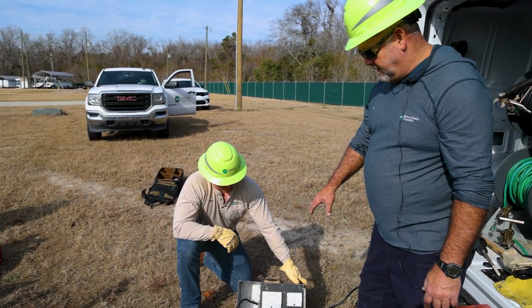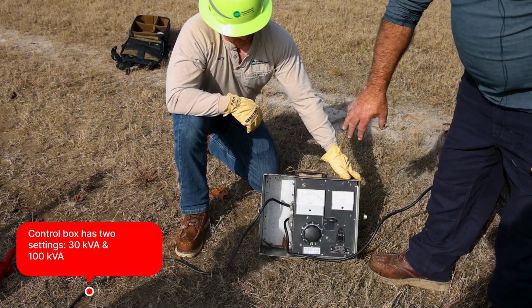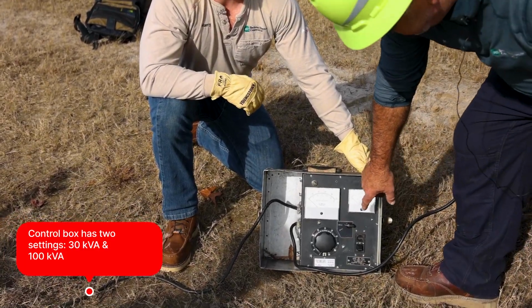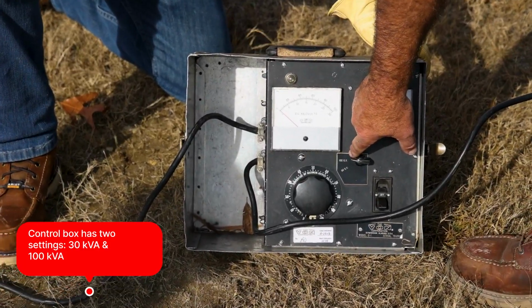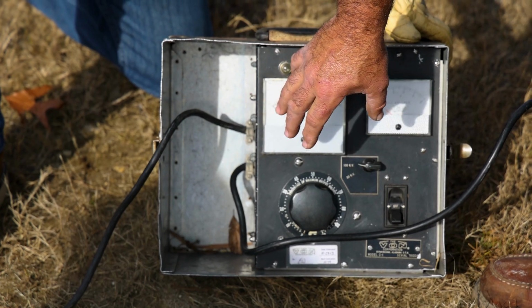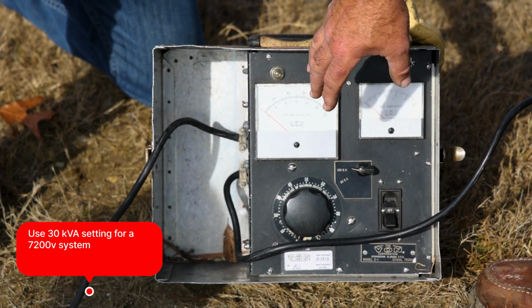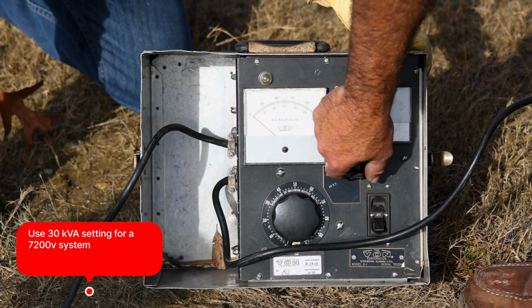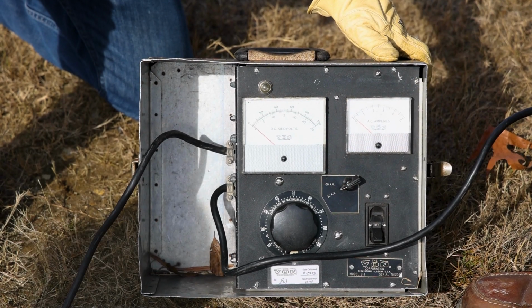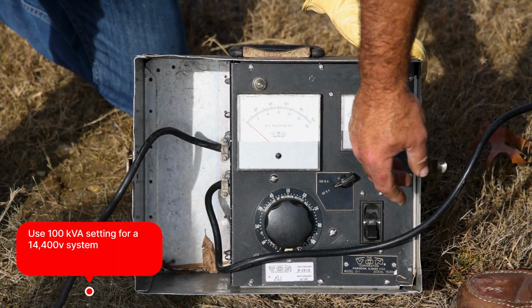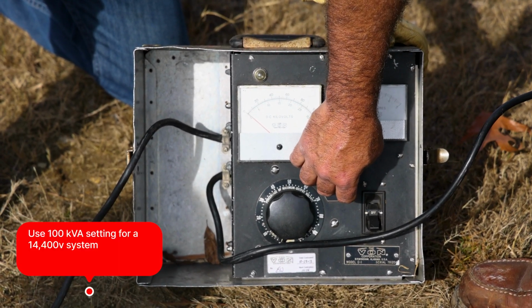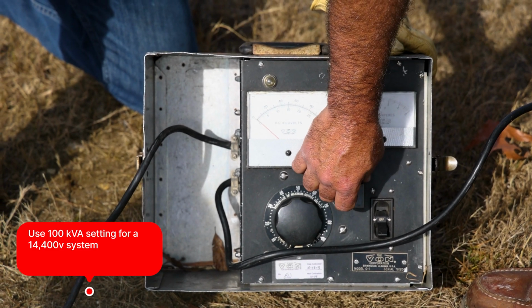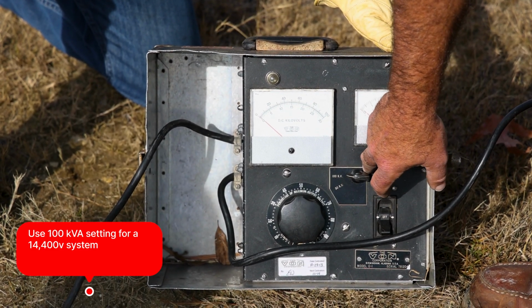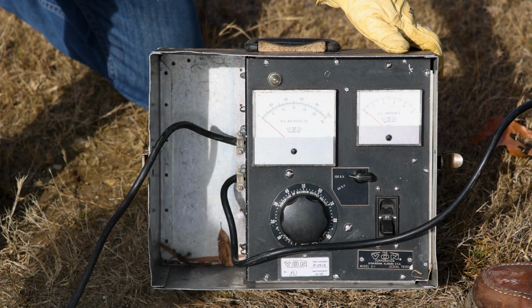This is your control box. This control box has two different settings on it. It has a 30 kVA and 100 kVA. If you're on a 7200 system that has 15 kV wire, you want it to be on the 30 kVA. When you're on a 14.4 system that has 25 kV or 35 kV, it has to be on the 100 kVA setting, so it'll send enough voltage for the thump.